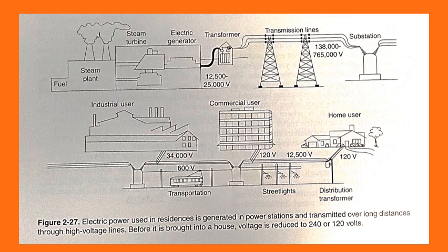The steam is produced by boiling water in a boiler. The heat for the boiler can come from many sources: natural gas, coal, oil, and uranium for nuclear fuel, which are the most common sources. Most electrical power is generated at 24,000 volts, and it is stepped up to 132,000 volts, or 230,000 volts, or even 345,000 volts at the power station.